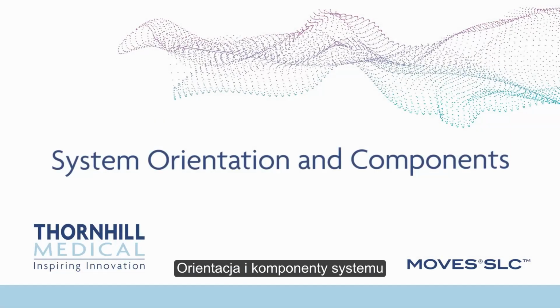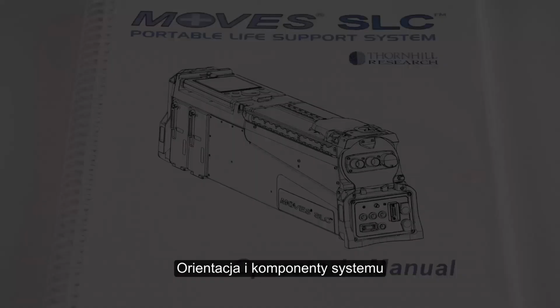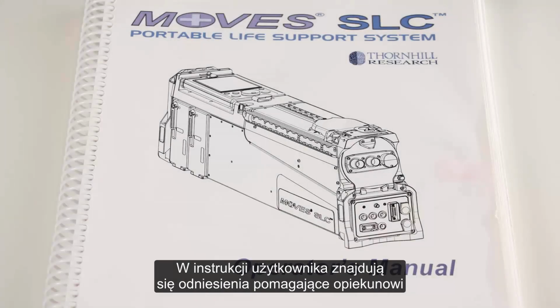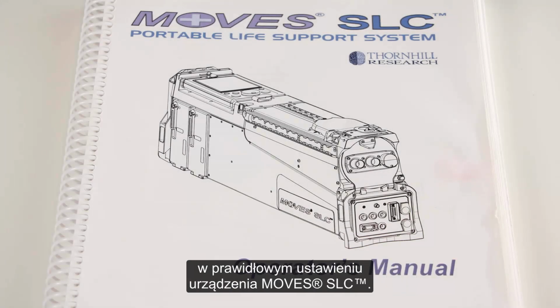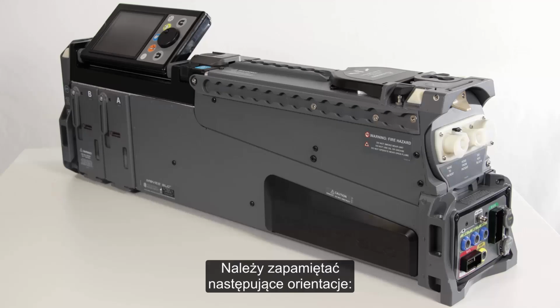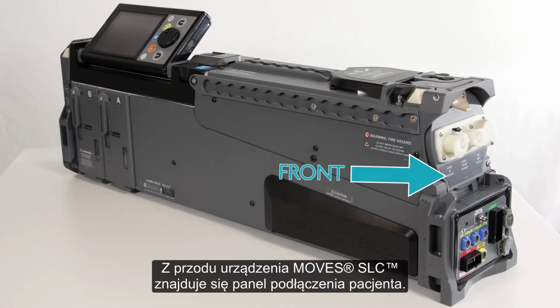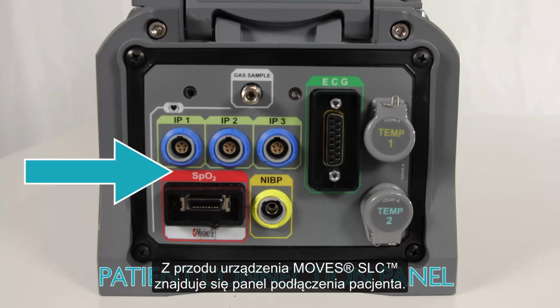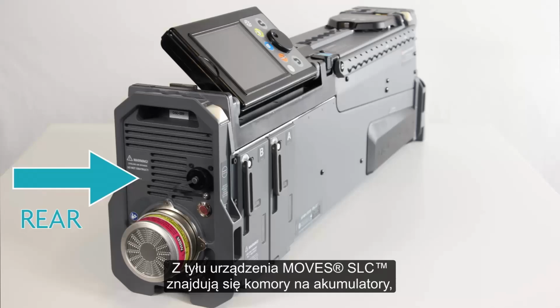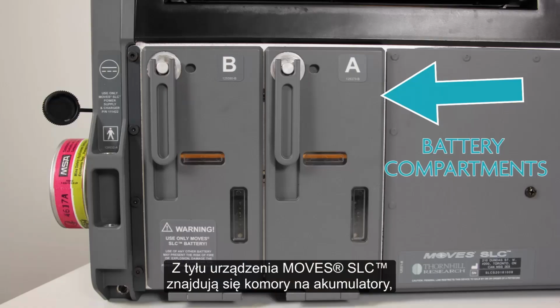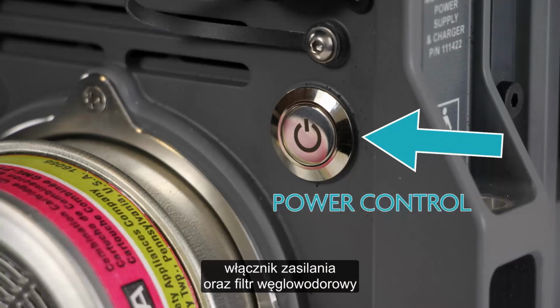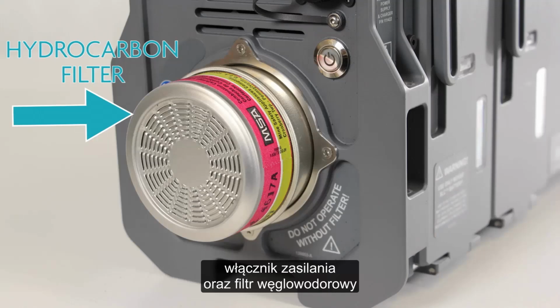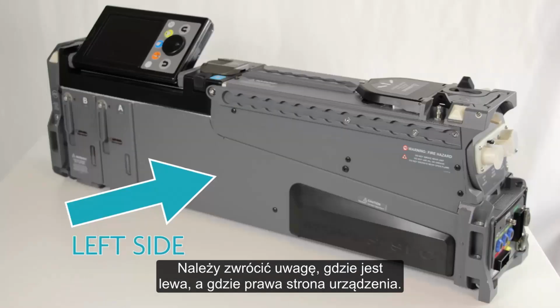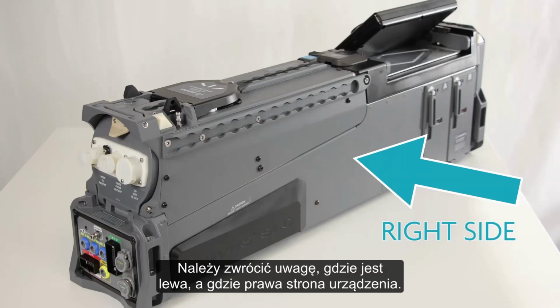System orientation and components. Throughout the user manual, there are references to help orient the caregiver with the positioning of the Moves SLC unit. The following orientations should be remembered. The front end of the Moves SLC contains the patient connection panel. The rear end of the Moves SLC contains the battery compartments, the power connection and control, and the hydrocarbon filter. Note the left side of the unit and the right side of the unit.